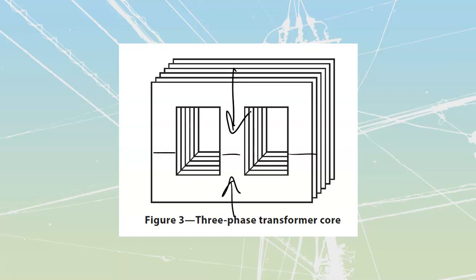It's going to be a laminated core. We do the laminations to reduce our eddy currents, made up of many thin laminations so that our eddy currents, which we can never completely eliminate, are able to operate on this plane, but because they're insulated with varnish, they cannot operate on these two planes. So we never get crossing in the vertical or horizontal like that, just these ones over here.